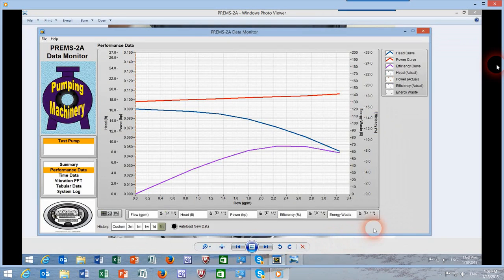So let's see how the screen looks, or several screens of the PREMS 2A system. Well, basically, the most common variable plotted on the screen is the head capacity curve. This is the blue line. HQ curve, horizontal axis is flow. Of course, it's very small flow, 2 gallons a minute or so for the little demo unit. Flow on the horizontal axis, and then vertical axis is head, power, efficiency, energy, efficiency of the pump, as well as energy that is utilized by the system.